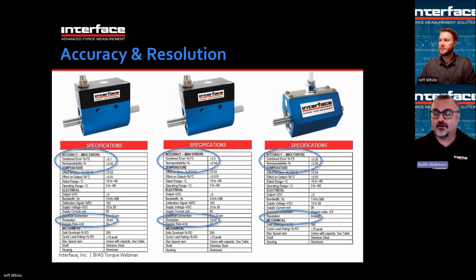Here are some examples of specification pages for various different torque sensors. So you can see, if you're going to be comparing, they have something called a combined error. You have 0.1, 0.2, or 0.25%. In the case of these torque sensors, there's their non-repeatability spec, which gets a little worse as you go from model to the right. And then we also have a resolution. Say the higher accuracy sensors typically are 16-bit or more.